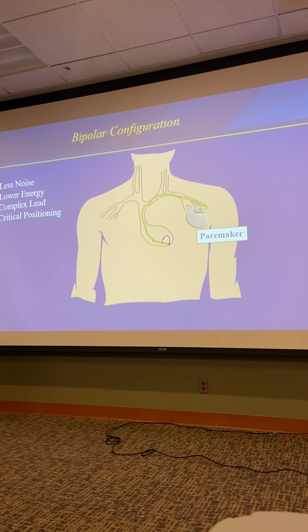It's got two metal conductors in it. Usually it's a single wire down the center, and then a braided wire going around it, like a coaxial cable, like the kind you have for your cable box at home. And that braided wire tends to be able to flex and move very easily. Positioning is more critical because the electrical circuit is confined to a very small area of the heart. If there's scar tissue, usually from a previous myocardial infarction, that won't work. So often we have to move these leads around the heart until we find a spot where the energy delivered in this very small space is reliably available to the rest of the heart.